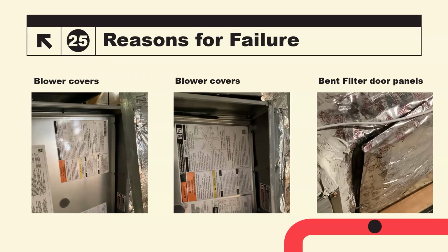That is within the standards that say whatever is allowed to be opened mechanically needs to remain as such when I do my testing. Sure, I can sit and tape all this stuff up. I can get a passing number, and then I'm going to sit and take all this tape off. All that did was prove that it could pass if it was installed correctly, but since it's not, it should be failing and it should be fixed.